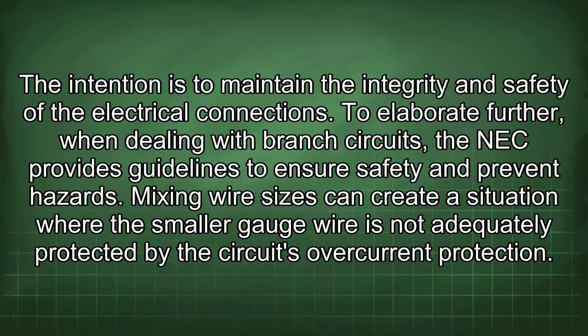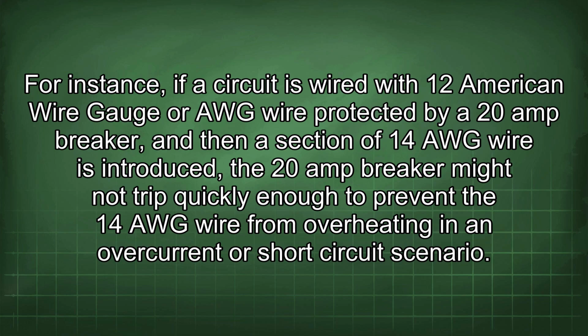To elaborate further, when dealing with branch circuits, the NEC provides guidelines to ensure safety and prevent hazards. Mixing wire sizes can create a situation where the smaller gauge wire is not adequately protected by the circuit's overcurrent protection. For instance, if a circuit is wired with 12 American wire gauge, or AWG, wire protected by a 20-amp breaker, and then a section of 14 AWG wire is introduced, the 20-amp breaker might not trip quickly enough to prevent the 14 AWG wire from overheating in an overcurrent or short circuit scenario.